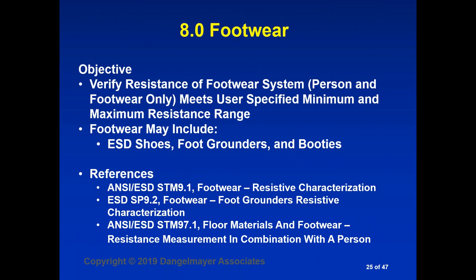Okay, another way of grounding people is footwear. We want to verify first the footwear itself, the person in the footwear. We want to make sure they meet a specified minimum and maximum range. Footwear may include shoes, foot grounders, booties, heel straps, lots of different ways of grounding people. Your references are STM 9.1, SP 9.2, and 97.1 floor materials and footwear, which is actually a resistance measurement in combination with a person.